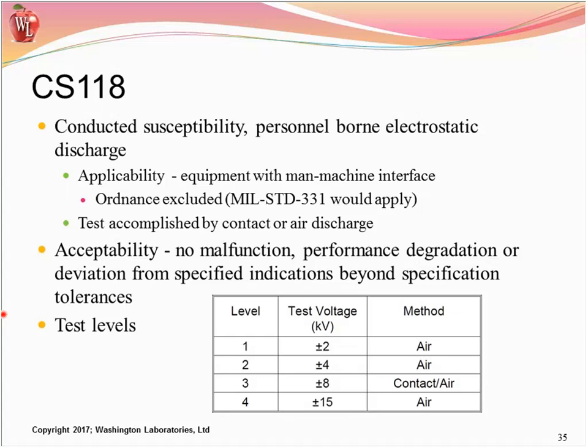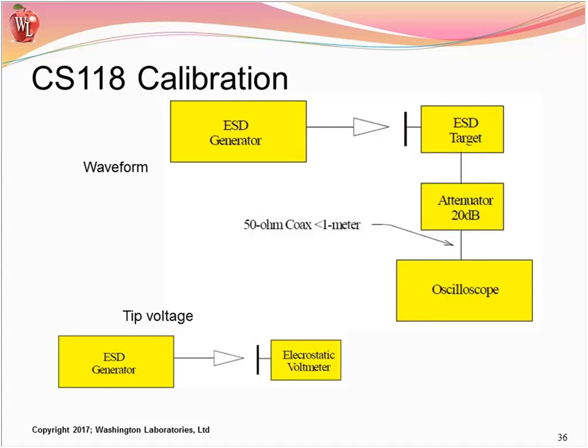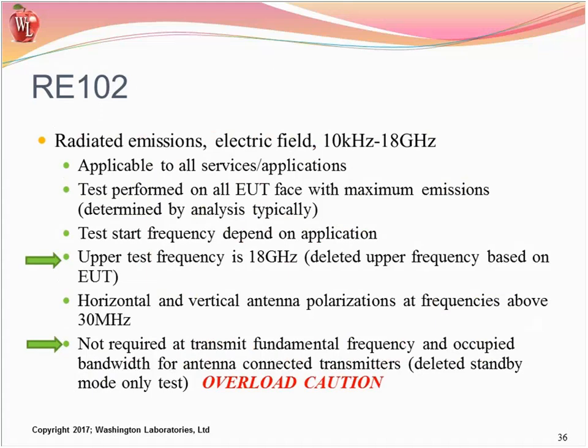Remember, conducted discharge lets you get better control of the waveform and repeatability. Air discharges compensate when you don't get a conducted path attached, no metal structure. So you'd use this air discharge and see if it breaks through the insulation. Several things happen with calibration as far as the waveform guidance, how much current you're getting, the waveform, the tip voltage, and so on. It's pretty clear on doing that, and the test target is something that's well defined. It's extracted right out. It's the same test target as the IEC 61000-4-2. So the idea is we're simulating the same thing for this. And remember, if you consider that 464, the system document, brought in electronic assembly ESD testing prior to it being in 461, this should show conformity.